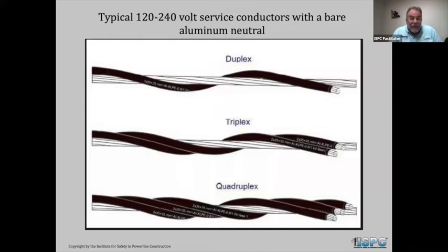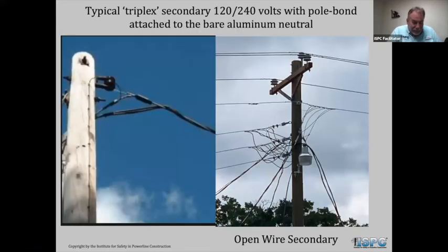All right. 120, 240 volt service conductors, sometimes maybe 277, 480, depending on the size of the customer and the voltage that they need. But we call the 2-wire a duplex, the 3-wire where you have 2 conductors and a neutral, a triplex. And then if it's a 3-phase, you have 3 conductors and the system neutral. They usually bond to the pole. I have the picture on the left showing how we bond that secondary neutral to the ground wire coming down.